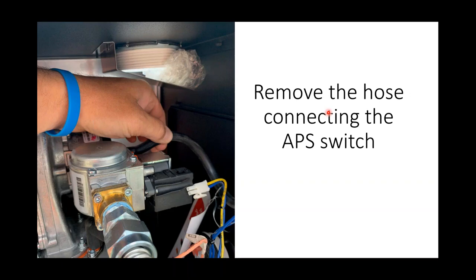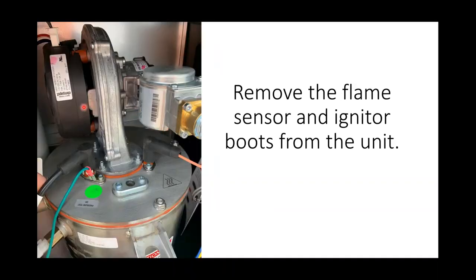Next, we're going to remove the hose connecting the APS switch. We're going to pull this hose off. That's on the negative pressure side of the gas valve. We want to make sure that we also return that when we put the unit back into service, or else we get an error 28. The APS switch would fail to close. Next, we want to pull the boots off the igniter and the flame sensor. Pull those, get them out of the way. They'll dangle down inside the cabinet. We'll replace them when we're done with the clean and service.